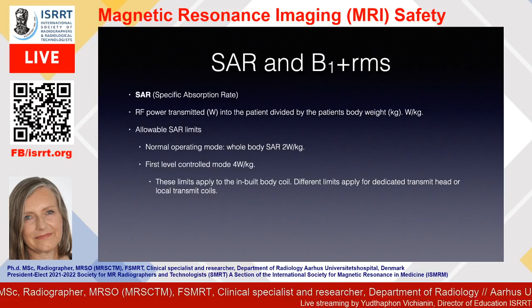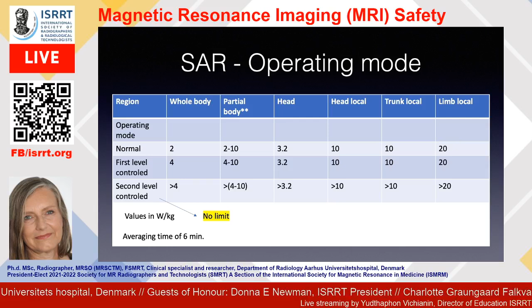These limits are for the inbuilt body coil, and different limits apply for dedicated transmit head or local transmit coils. And I'd like to show you this scheme because normally we go for normal or first level controlled mode, but actually there's also something called the second level controlled mode. And I would say you should never use that on a human being, because here you can see there's actually no limit. You can go above the 4 watts per kilo. You can also see that there are different limits for local SAR than for whole body SAR.